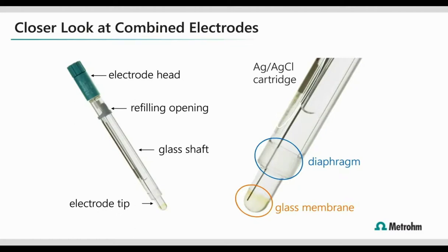The general parts of the sensor are the electrode head, and this is where the electronic connections are made, and definitely an area we want to protect from getting wet with sample or titration reagents. Following it down, next we have the fill port or a refill opening. So the reference electrode system needs constant care and feeding with electrolyte solution, and this is where we access that. The shaft, or glass shaft, or sometimes plastic, depending on the type of electrode, is just the main body of the electrode. And while we want to keep this area and below rinsed of the sample between measurements, there's no actual measurement or any magic happening here, right? But give yours a look in the lab. Get familiar with how it's supposed to look when it's healthy. That way, if it does endure any cracks, you'll know how to see those right away, because those will affect how the electrode works.